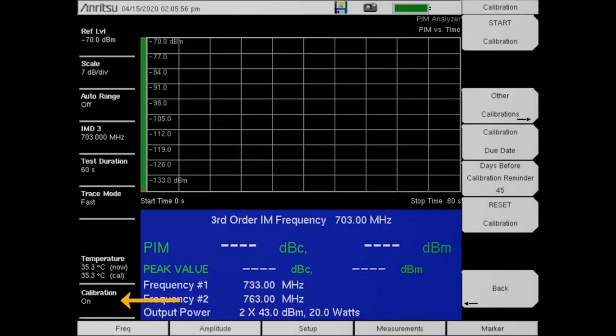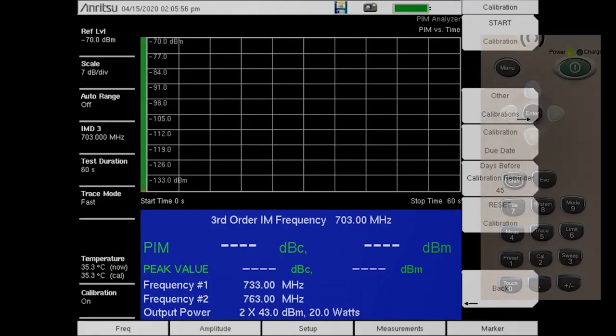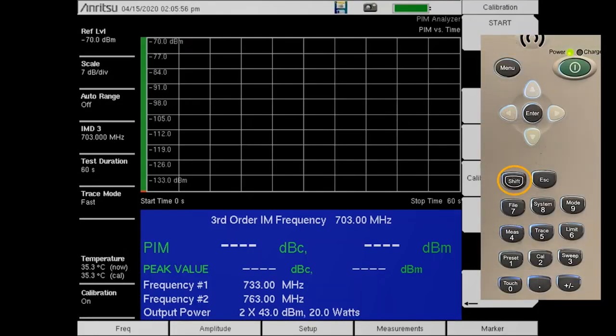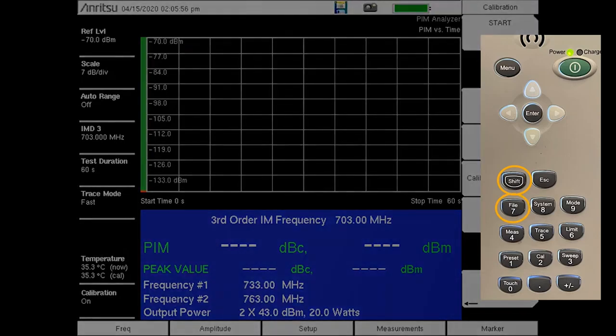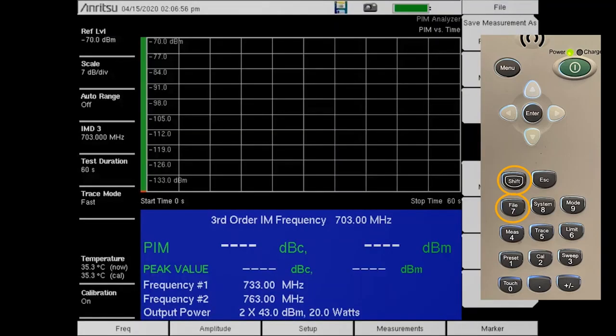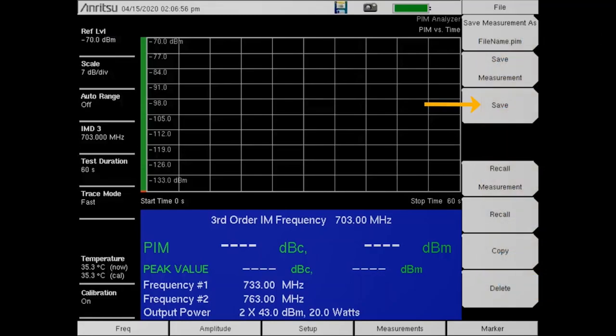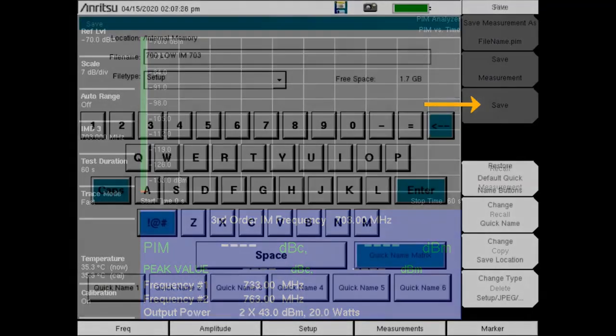Once the calibration is complete, we will save the setup file. Because calibrations are saved with the setup, saving the setup allows for the setup parameters to be retrieved with the calibration. To save the setup, press the Shift key on the keypad followed by File. Then press the Save button. Be sure to enter a name which reflects the IM location this setup uses.